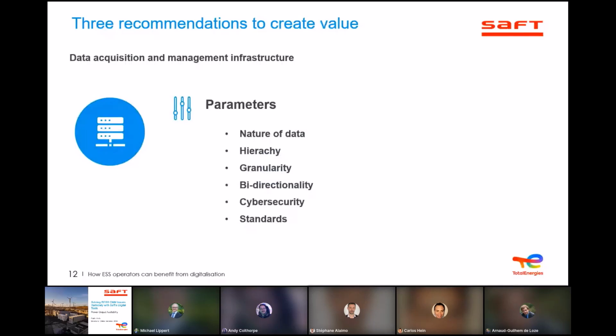On the first point, data infrastructure, there are multiple parameters to be taken into account, such as the nature of the data: what kind of data do you want or need to collect? The hierarchy of this data—cell level, module level, string level, system level, or all of them? The time granularity—do we acquire data in seconds, 5 seconds, minutes, hours? Things like bidirectionality, cybersecurity, and international standards need to be taken into account. By doing this, we ensure operators can generate, in a reliable manner, accurate and high-quality information for their operations.